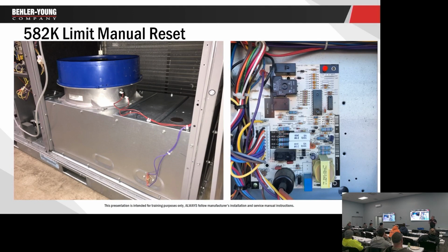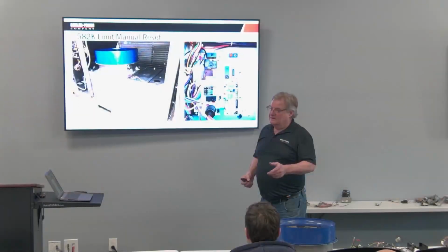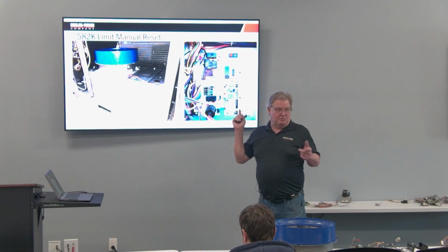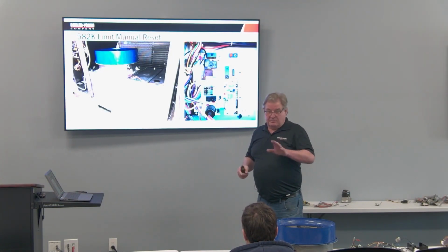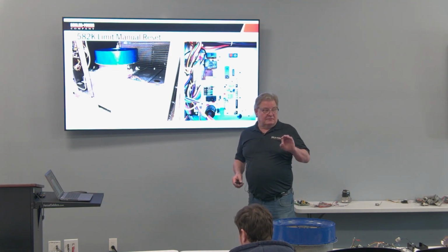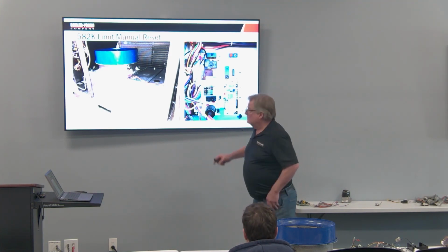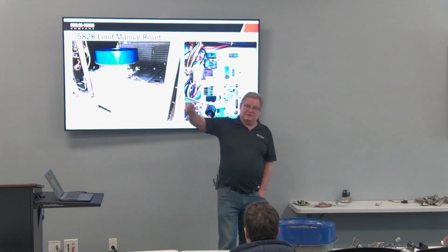So if you have a 2019 or earlier, it will have this manual reset limit. And they're still there. You'll still come across them. I got a call on one the other day. So on this unit, the 24 volts went through the jumpers for the smoke detectors and went to there. So you'd walk up, you got no 24 volts. Go look in the blower compartment. If you got an older unit, it might have that limit in there. Reset that limit. Now, if that limit tripped, something happened because that unit's been running since 2019. And if it's tripping now, there's no point to take that limit out. Okay, because what we have now is an auto reset limit. So the units today have an auto reset limit there. And guess what? They're no longer red wires, they're now purple wires because they're in the limit circuit.